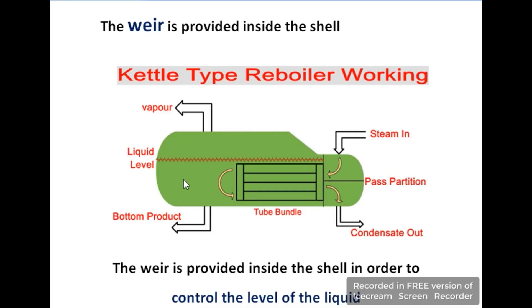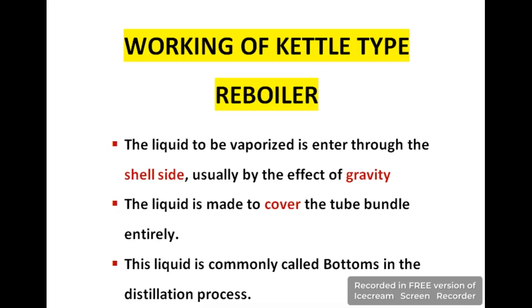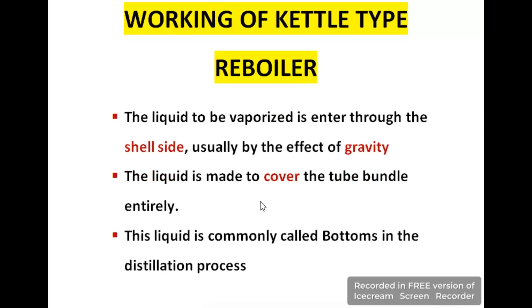Here you can see the liquid level line, and that level is always maintained with the help of this weir. Now we will discuss the working process of the kettle type re-boiler. The liquid to be vaporized enters through the shell side, usually by the effect of gravity. This means the feed enters the shell by gravity and no mechanical equipment is used for this process. This liquid, which covers the tube bundle, is commonly called bottoms in the distillation process.